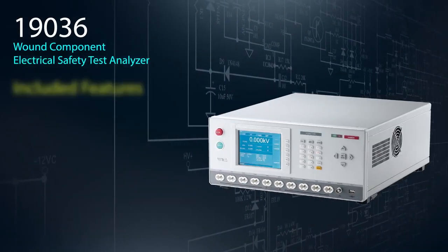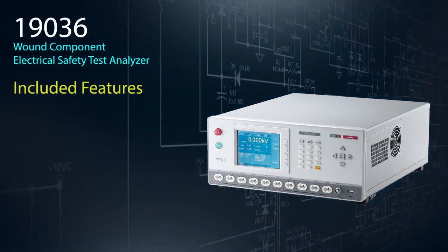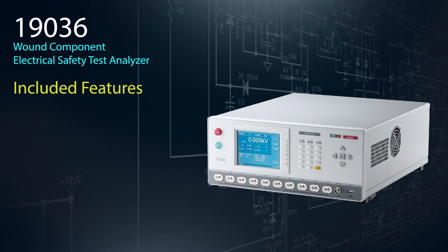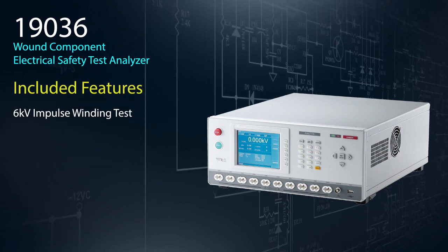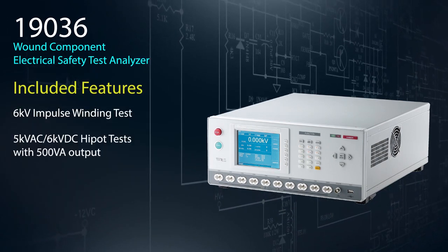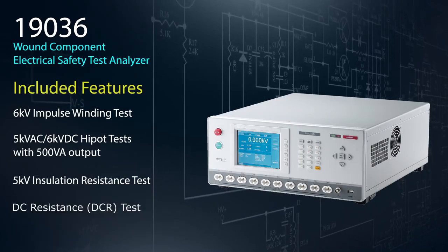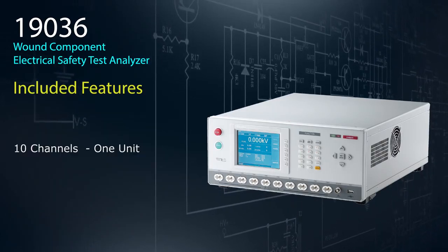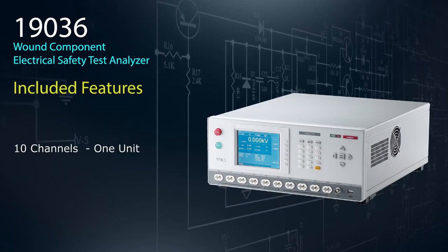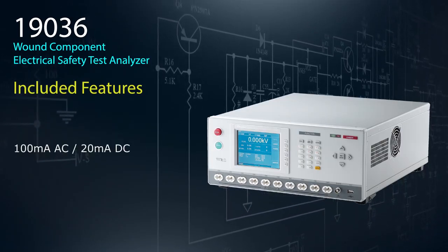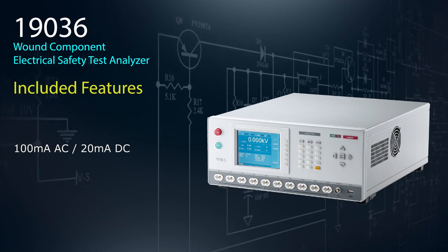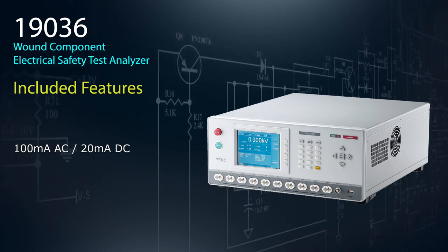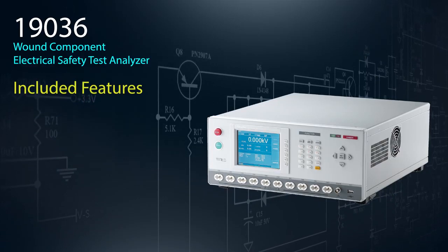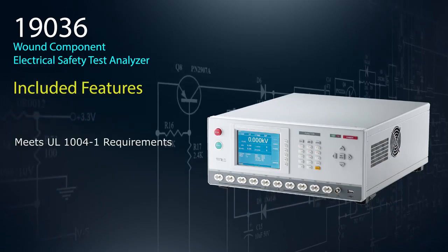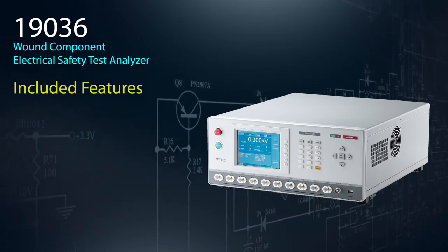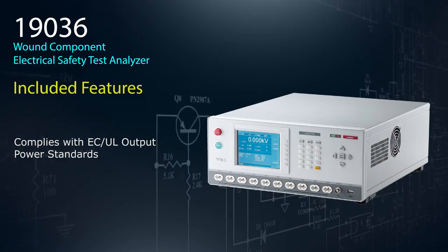The Chroma 19036 is the industry's first wound component electrical safety test analyzer that combines impulse winding, also known as surge testing, AC-DC hipot, insulation resistance, and DC resistance test measurement functions into one 10-channel unit. Capable of outputting and measuring 100 milliamps AC and 20 milliamps DC, the 19036 is applicable for testing to high-power motor standards like UL 1004-1. Its 500 VA design is also compliant with EC/UL output power standards.